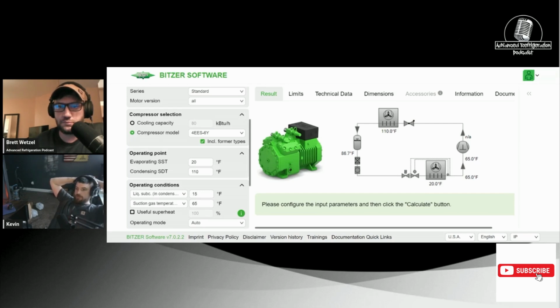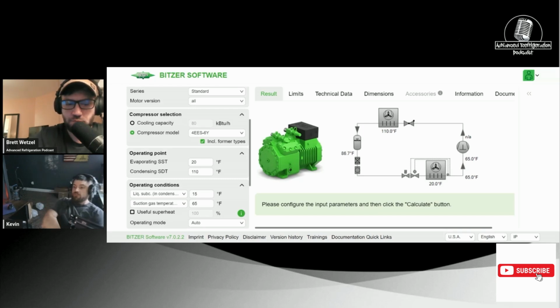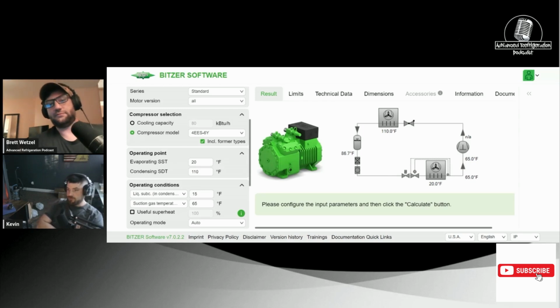Now, when you're entering this information, this is where it's key. Do not enter what the rack legend is for the suction and saturated suction temp and the saturated condensing temp. You need to enter what the actual compressor is running at this time. So if it's a plus 20 design and it's running at plus 22, and it's running an 85 degree condenser and it's sized for 115, you put the 85 in and the plus 22 in. You want to test it at what it's running right then and there. And then also suction return gas. This is extremely helpful when you're troubleshooting discharge issues. You need to get an accurate suction return gas temp at that compressor, not the one off the rack. Just throw a probe on there and get the actual suction return line temp. This will help you calculate discharge temperatures.